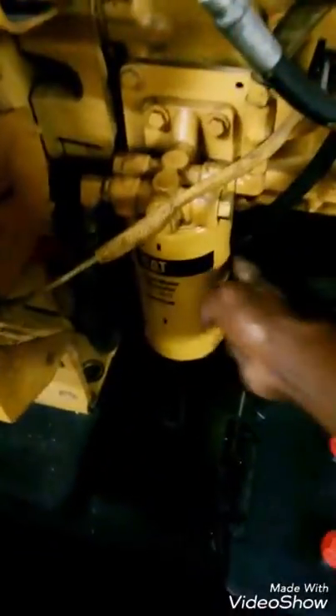On this side, you get a better look at the generator. This is your flywheel. The generator is connected in here, turning your mechanical energy into electrical power. You have 2 phases connected, 3-phase generator. Your battery connections, your starter solenoid, your starter itself, turning your flywheel, which will then turn your crankshaft and then ignition. And of course your RPM is turned into electrical energy and distributed to the building. You have your alternator here in the casing. What else? You have your fuel water separator here. You also have one out here.